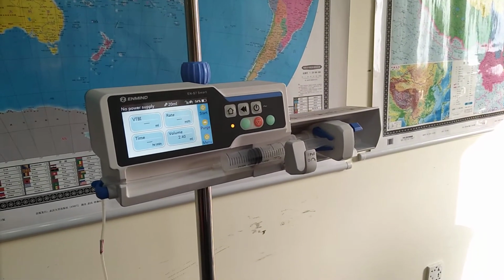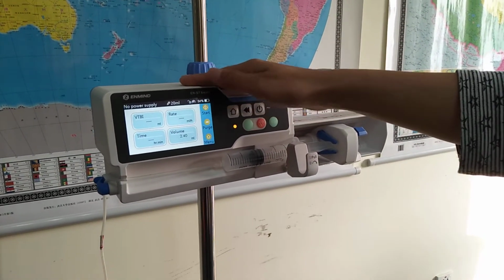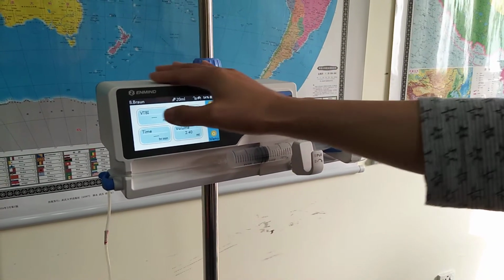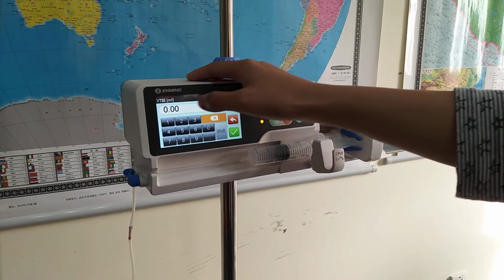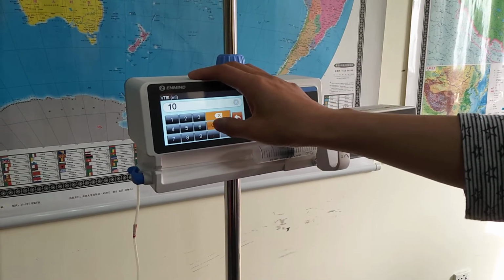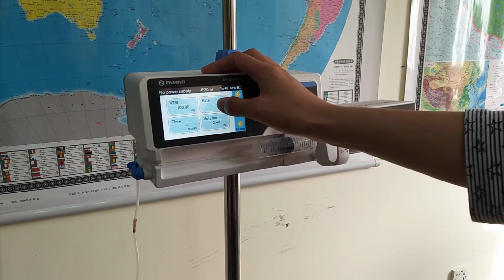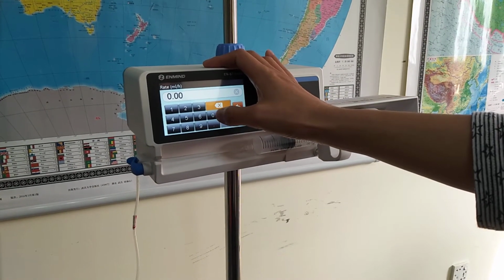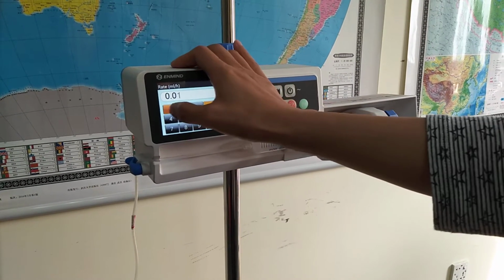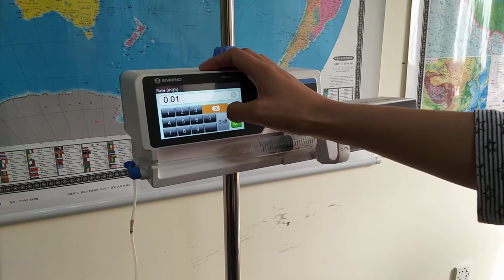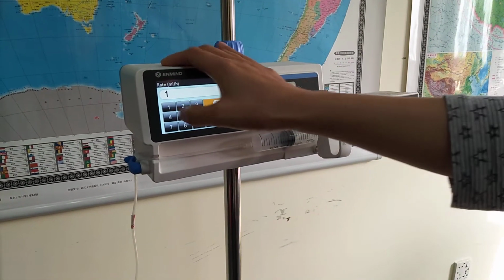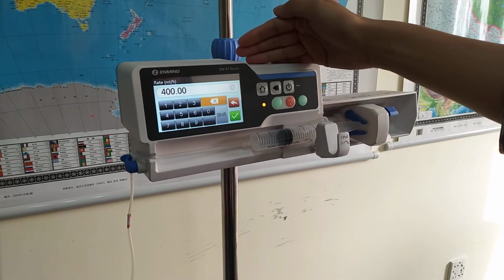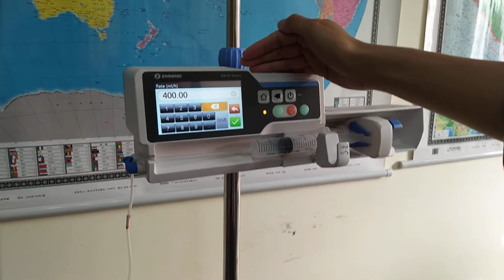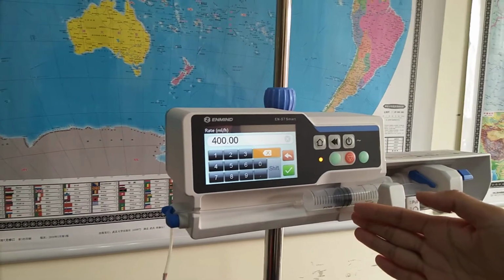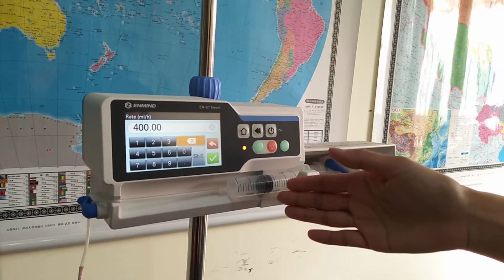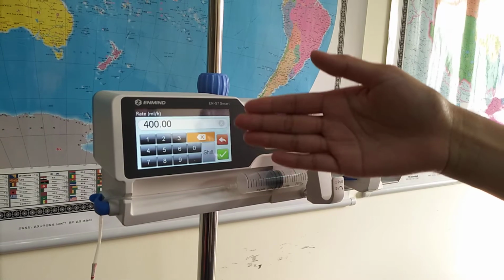Our milliliter per hour mode combines timing mode and rate mode. We now give VTBI, volume to be infused, like 100. And then input the rate. The minimum rate is 0.01. And the maximum, let's give 1000. You can see it goes back to 400 milliliter per hour. So this is a 20 milliliter syringe. The maximum speed is 400.